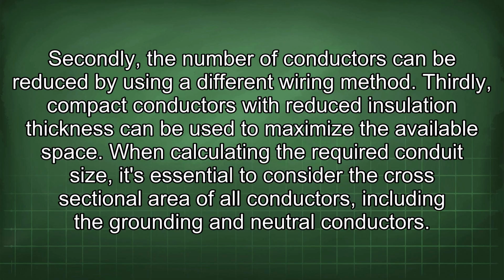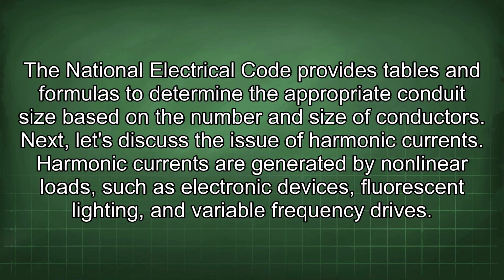When calculating the required conduit size, it's essential to consider the cross-sectional area of all conductors, including the grounding and neutral conductors. The National Electrical Code provides tables and formulas to determine the appropriate conduit size based on the number and size of conductors. Next, let's discuss the issue of harmonic currents.